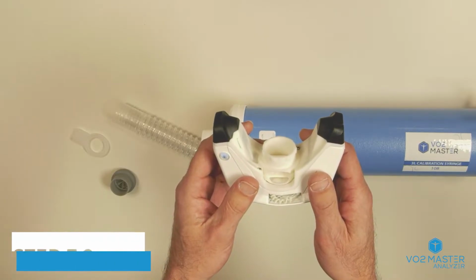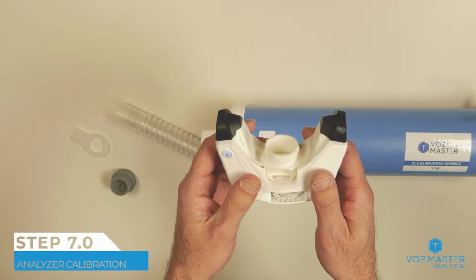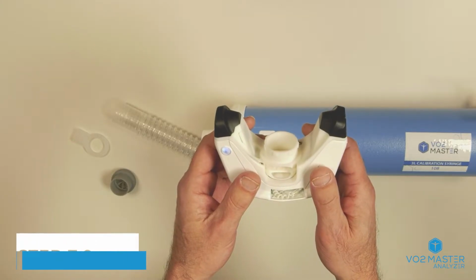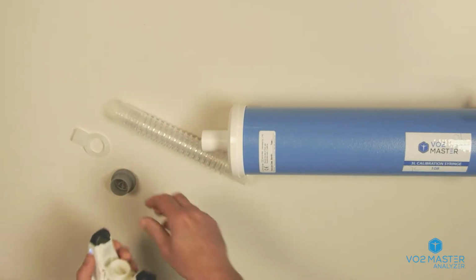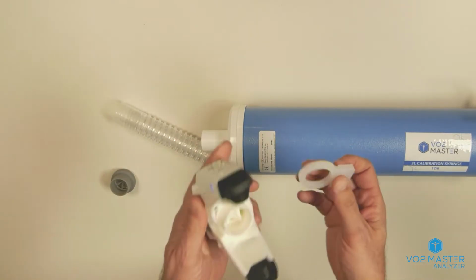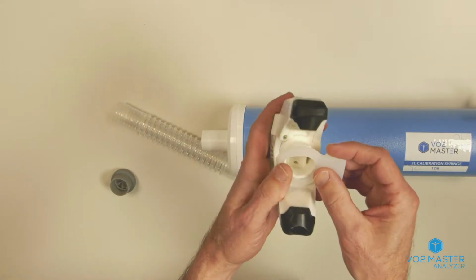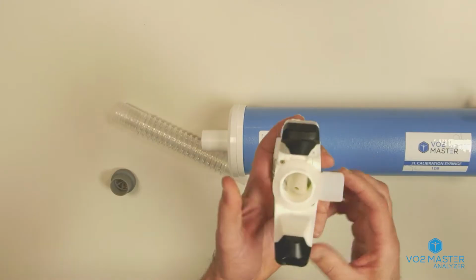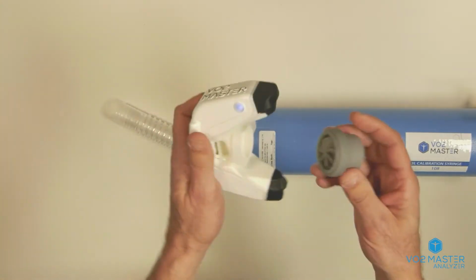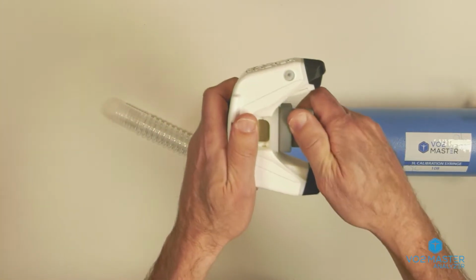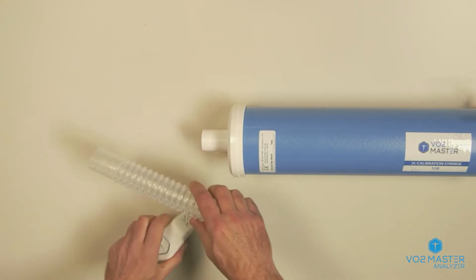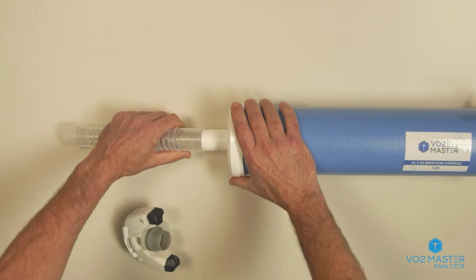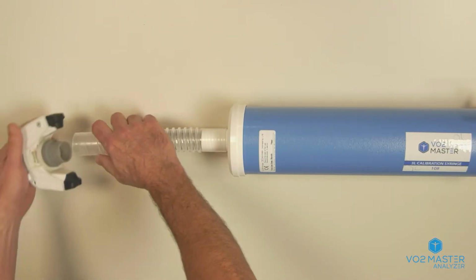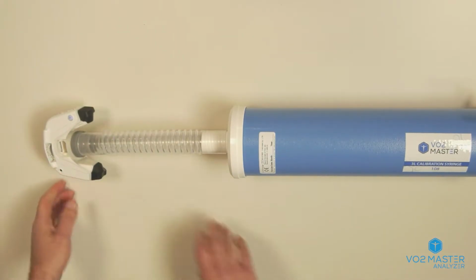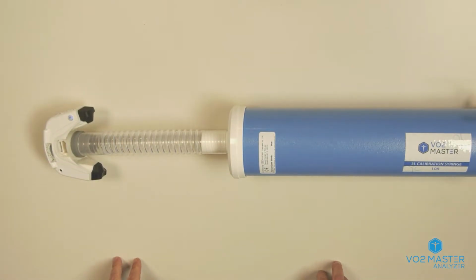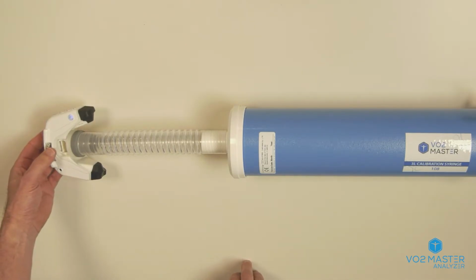Now we're going to calibrate the VO2 Master Analyzer for flow. With the filter inserted and the chosen user piece in place, we'll use the supplied adapters to attach the analyzer securely to the calibration syringe. First, we put on the silicone seal with the tab pointing up. Next, attach the user piece adapter to the user piece. Then we put the shock dampening hose onto the calibration syringe, followed by the user piece adapter, making sure that the tab is pointing down and the intake port is pointing up. At the same time, ensure that the user piece opening is still in the middle of the analyzer port.